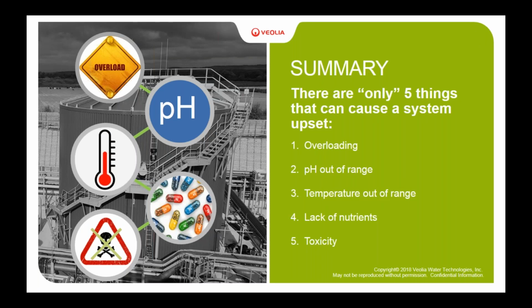Okay. Thank you, Jill. So just to go over again the 5 main things that are going to cause a system upset in an anaerobic reactor, as Jill pointed out: overloading, most likely due to some type of spill of product in the factory, is the major contributor typically to overloading. And pH out of range on the high side or the low side: a caustic dosing pump being put in manual and being left on and going high, a caustic line plugging due to freeze issues because caustic freezes at 60 Fahrenheit, or running out of chemical.